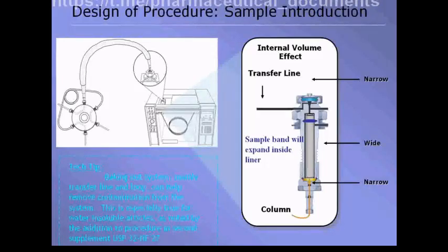But also, another tech tip for trying to implement this method would be baking out the system. So bake out the transfer line and loop between analytical batches. What that means is increase temperature to try and remove any type of condensation. This is especially true for the water-insoluble article option, where you use DMSO, and is actually noted as an addition to the procedure in the second supplement of USP 32-NF27.